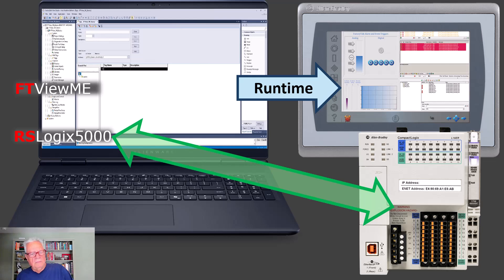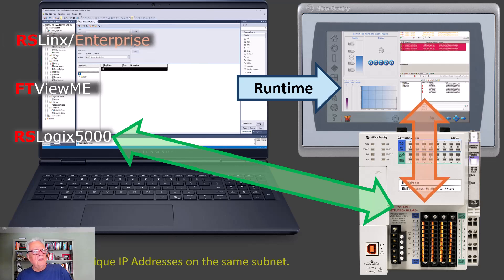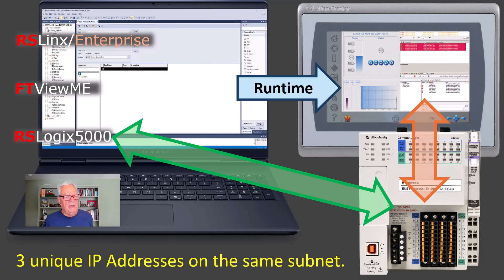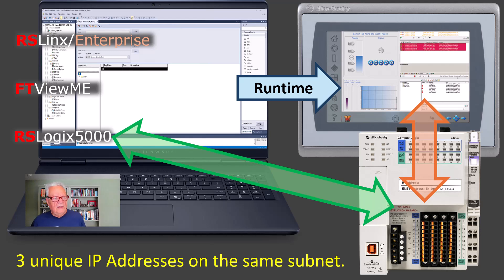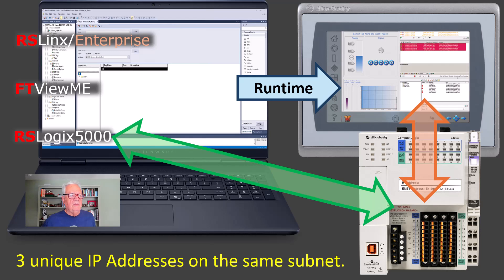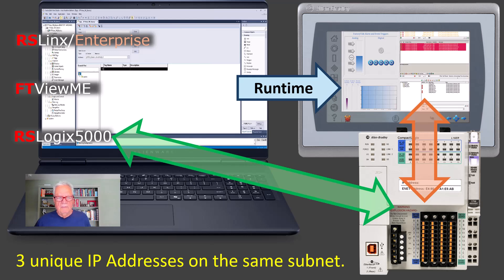However, what you're going to end up doing is you're going to download the Factory Talk View ME project by way of a runtime to the Panel View, and then before you get away, you have to go into RSLinx, specifically Enterprise, and you have to set up the communication, because you've got three unique IP addresses here. Your laptop, which is not in play once you commission this project in the field, but while you're developing it, you've got the IP address for the laptop, the IP address for the Panel View plus, and the IP address for the Compact Logix. You actually go into RSLinx Enterprise, and you set up the communication.